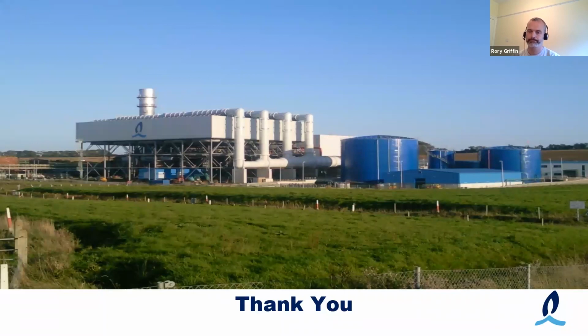Okay. From James again, what is the station power consumption overhead, and which power does the station itself consume? So typically 1.5 to 2%. For example, if Whitegate was exporting 440, it's probably generating 450. So that would be 1.5 to 2% of the gross power consumed.